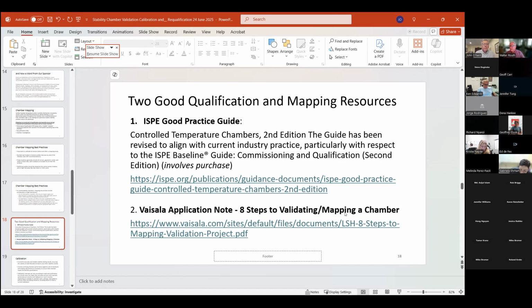Okay. Any other comments? The only thing I would add is, when we're talking about ductwork, I would do a risk analysis on the change of the ductwork, because that is the most likely thing that would cause an issue with its validated state. One thing I will comment on as well, and I've been questioned on this, is chamber shelving configuration. A lot of folks will add rolling carts in the chamber, and as they relocate those rolling carts within the chamber.